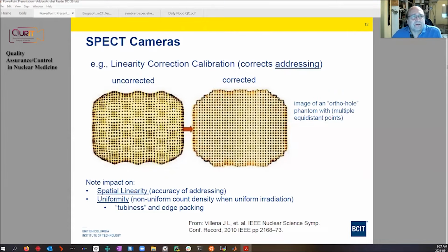On the left is a gamma camera that is irradiated using what's called an orthogonal hole phantom. So think of getting a rectangular piece of lead the same size as the detector and then drilling holes at regular intervals, every few millimeters. And so what you should see is a pattern of radiation hitting the detector at uniform intervals, dots evenly spaced in every direction.